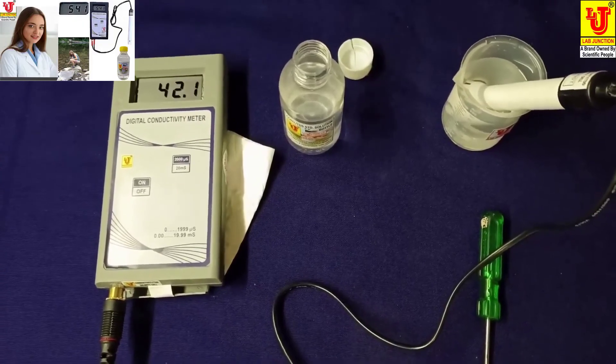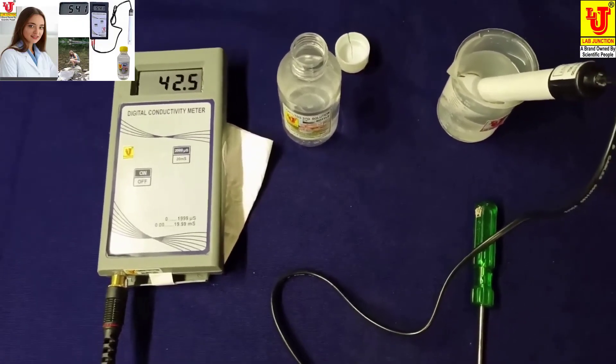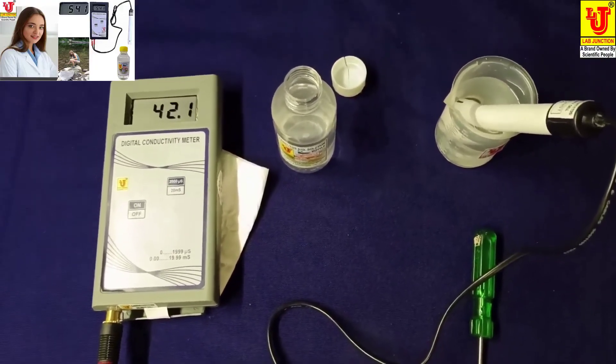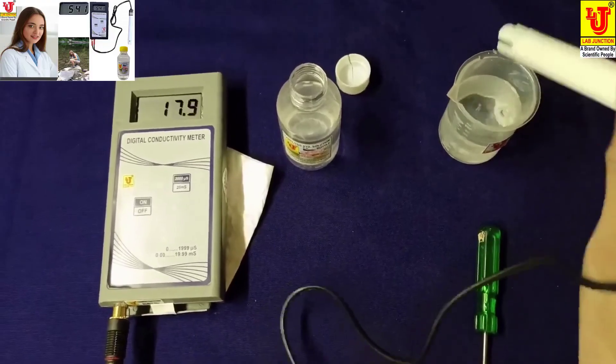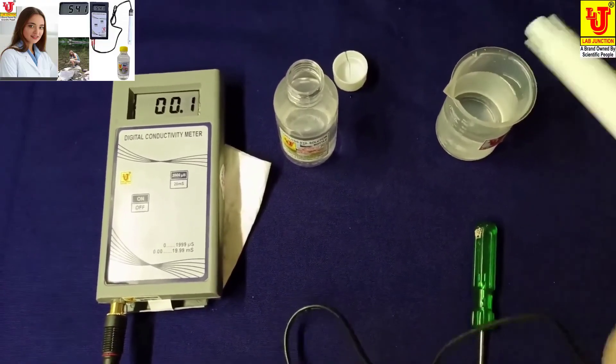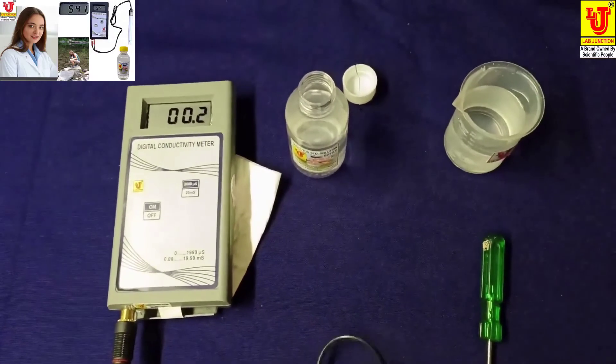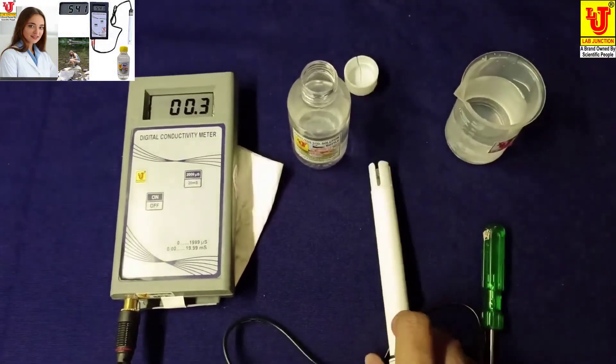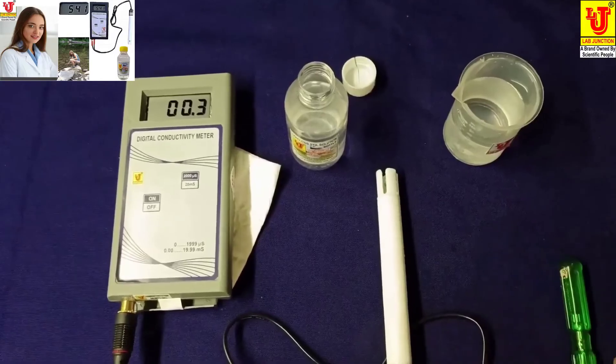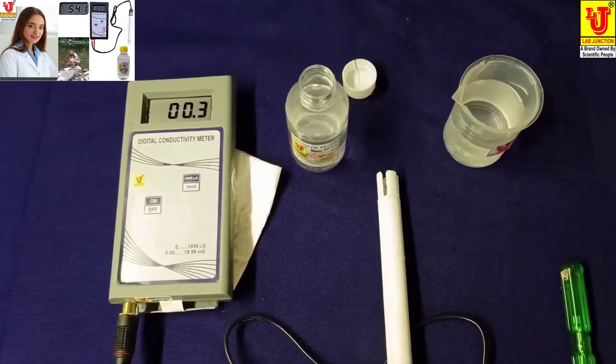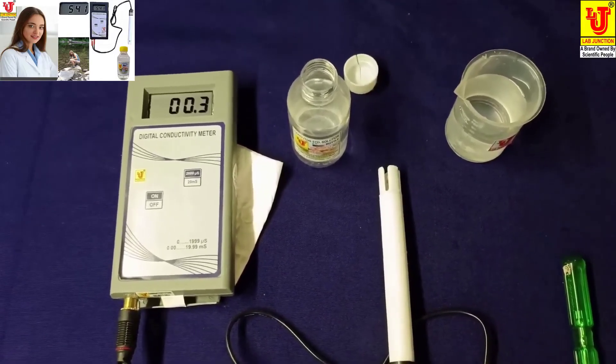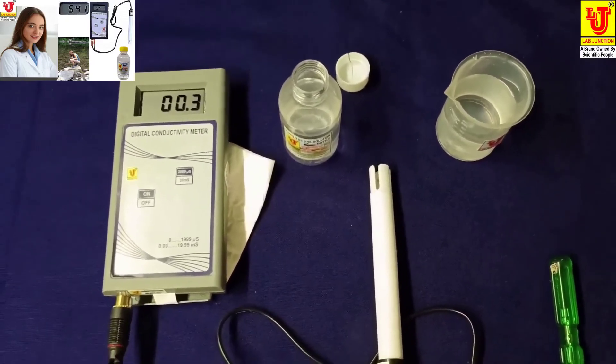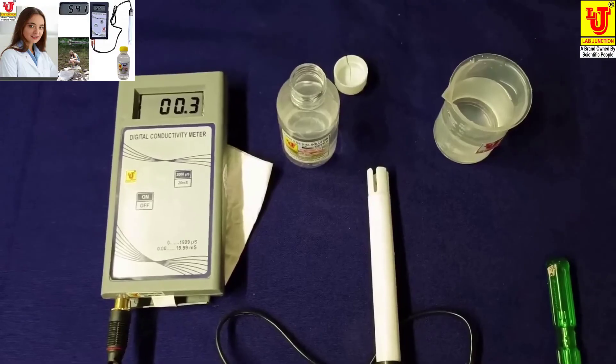After using all these precautions, please store dry conductivity cell after washing with distilled water. When you want to use this digital conductivity meter, please dip your conductivity cell before 24 hours.